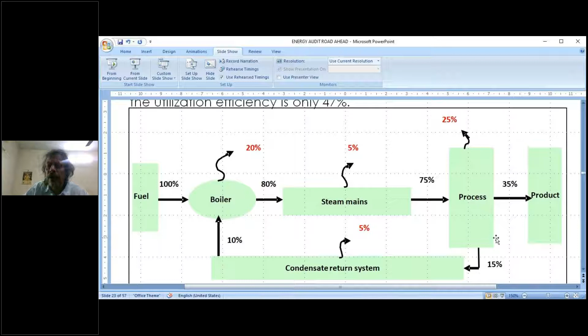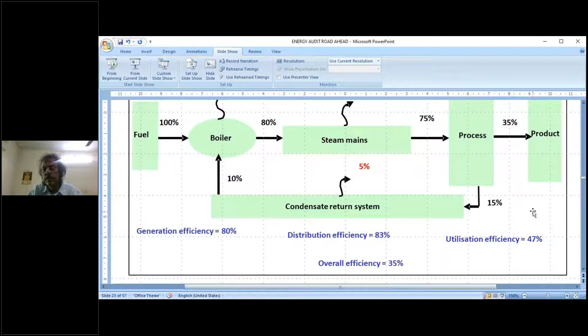So if you see the generation efficiency, the boiler itself is 80%. Then distribution from the boiler to the final process where the steam is delivered, in between the pipelines, is about 83% efficient. That means a 5% loss if you take. Utilization efficiency is only 47%. That means this is the place where maximum potential lies for energy savings. So you need to focus on that.